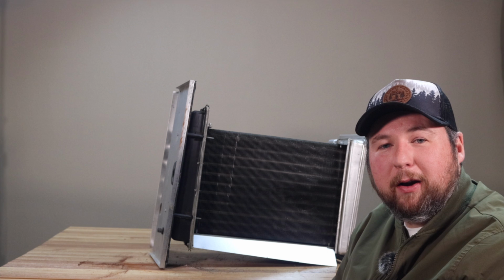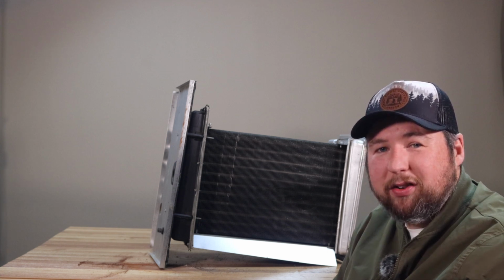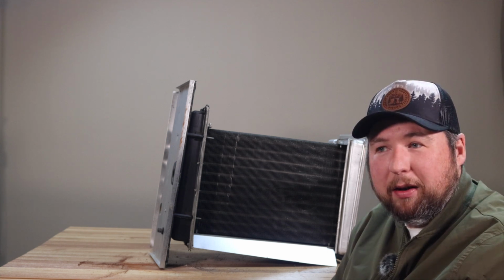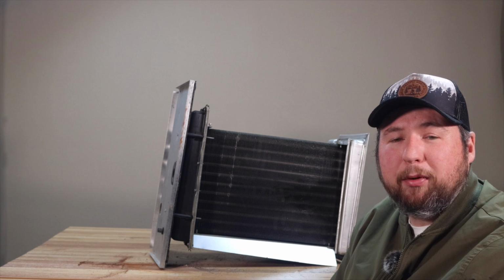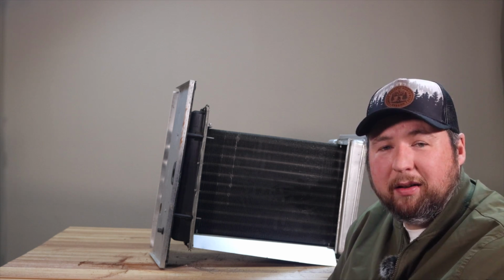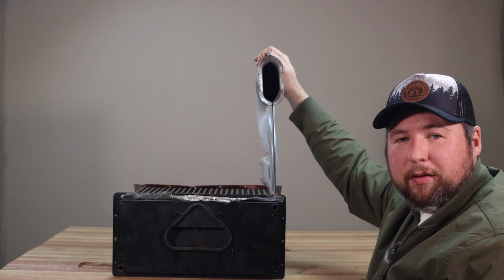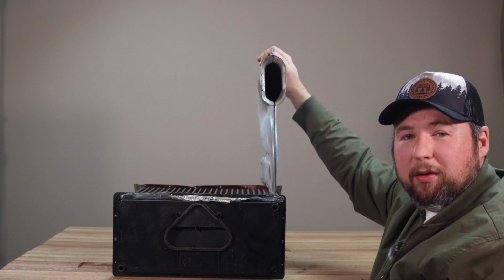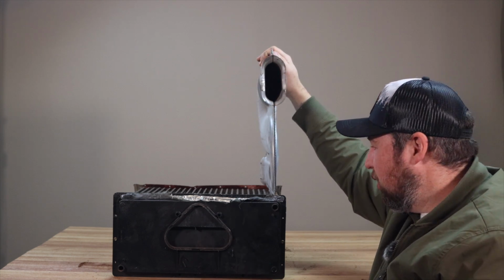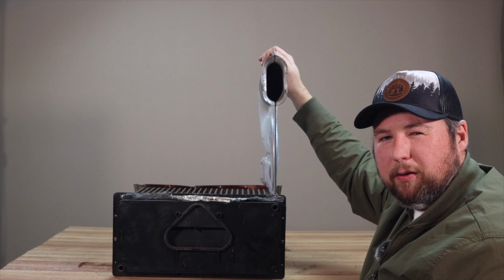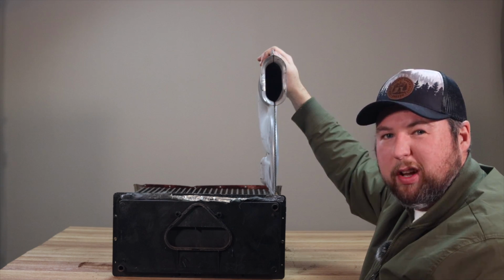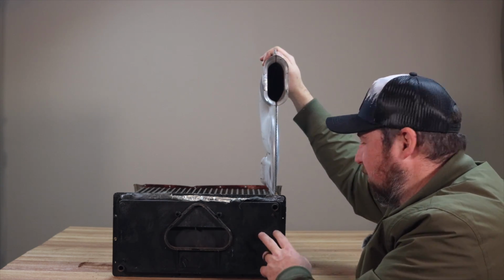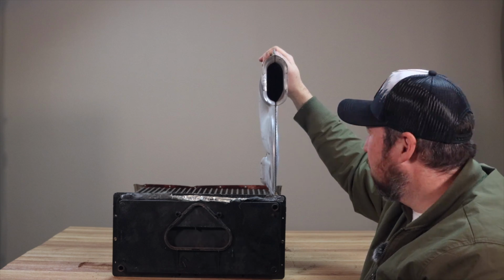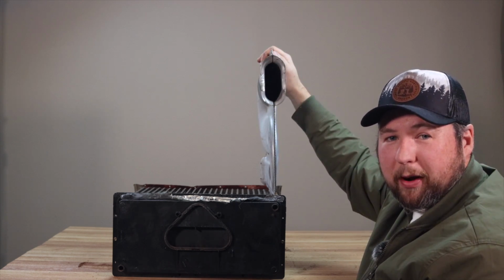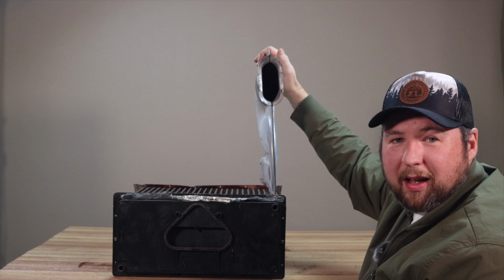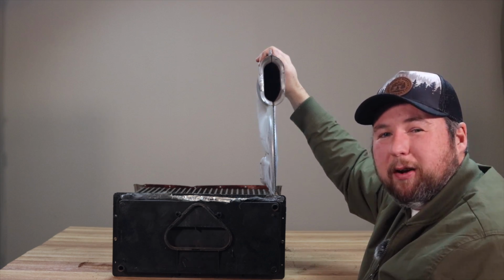So let me show you Carrier's older secondary heat exchanger style, and we'll use that as an example of what can go wrong with a 90% heat exchanger. So this is a Carrier older style 90% heat exchanger. I think they've switched it over to your standard tubular, because this one seems to have a lot of issues. I'm not 100% sure if they're still using it or not. I really hope they're not, because it's a terrible design. Some points of it are terrible, but anyway.